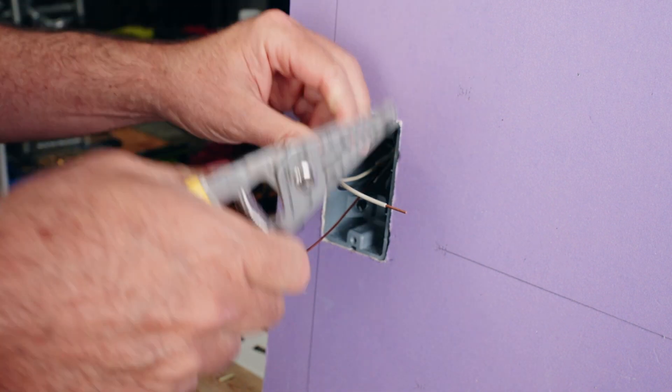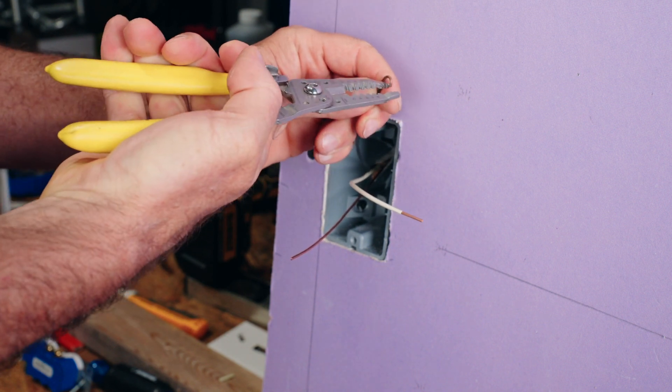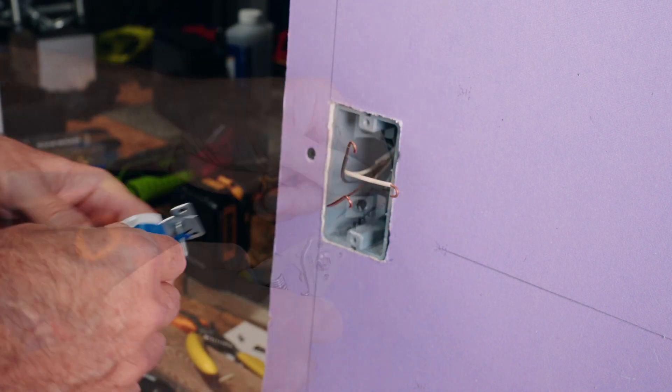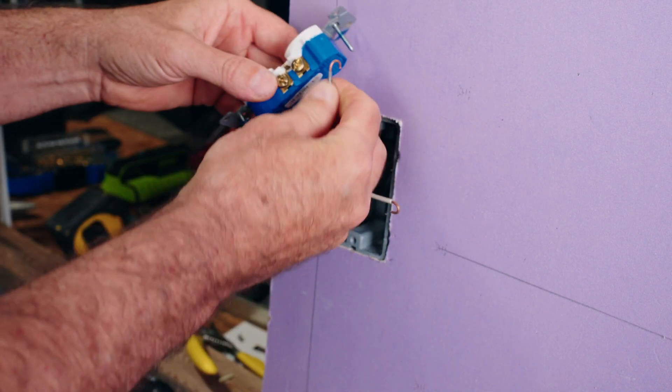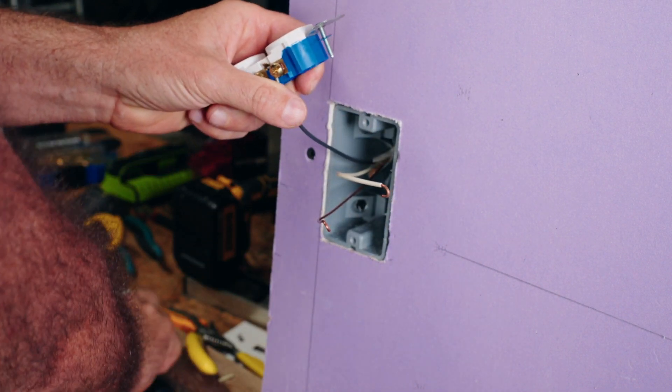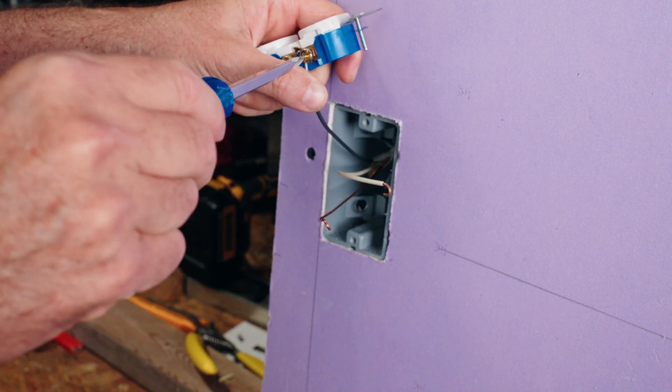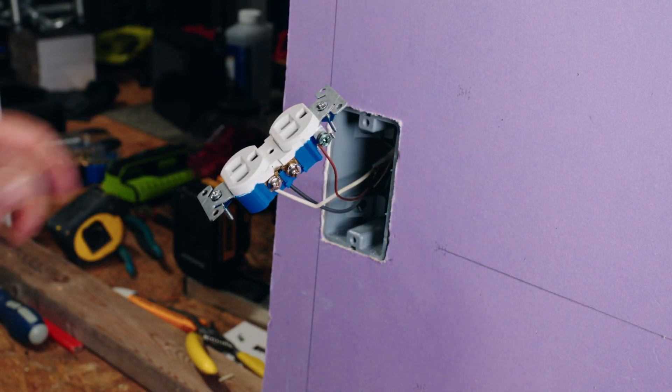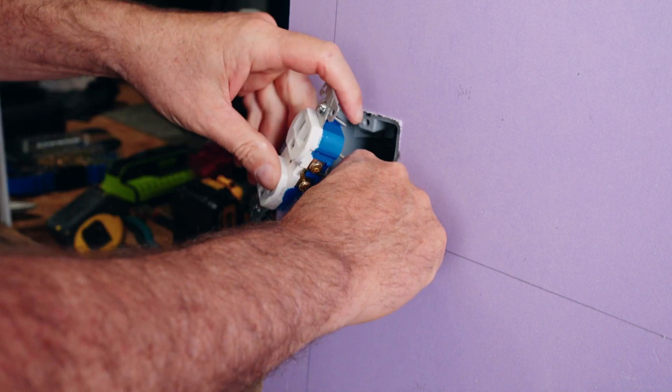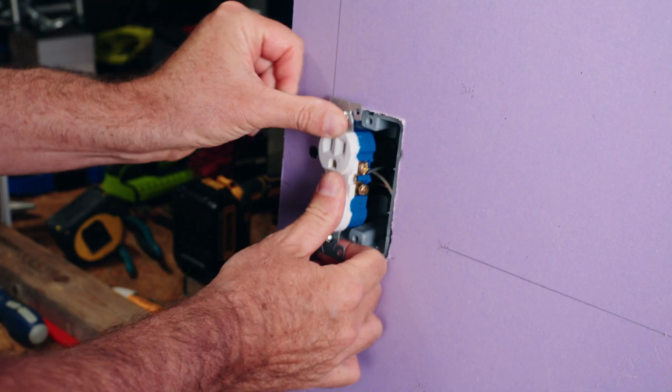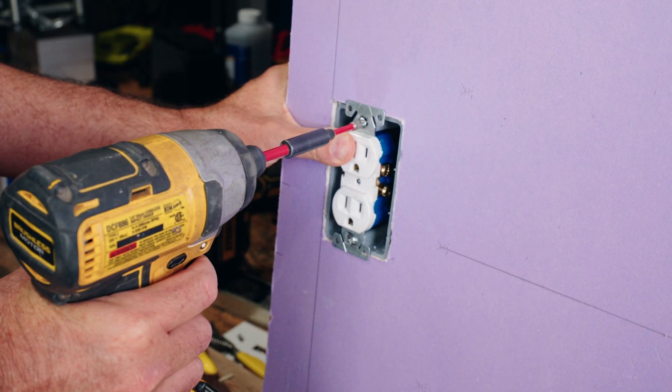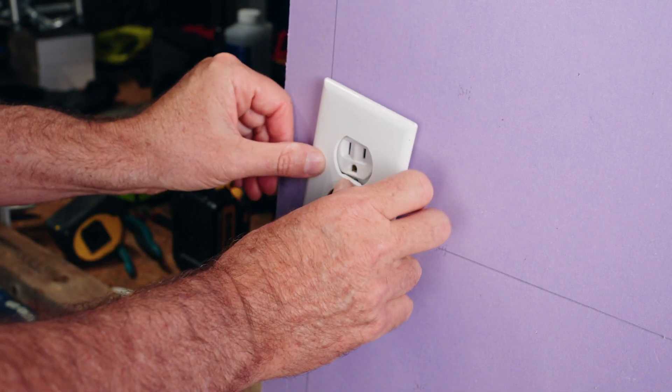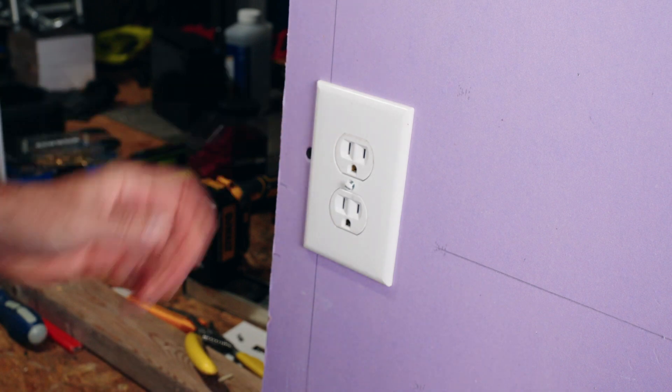I do like to bend these into a loop instead of doing the backstabbing, as I was explaining earlier. Just like any other plug, hot goes on the brass on the right, neutral goes on the silver screws on the left, and the ground is on the green screw. We'll fold up our wires nice and neatly and stuff it in the box. We'll put our cover on, and then that part is ready to go.